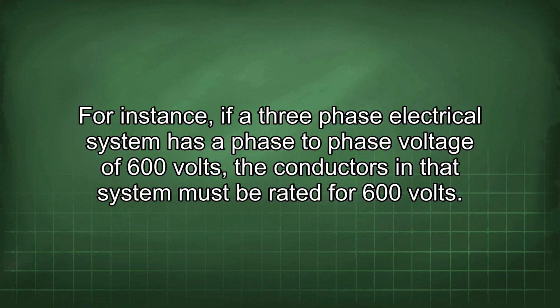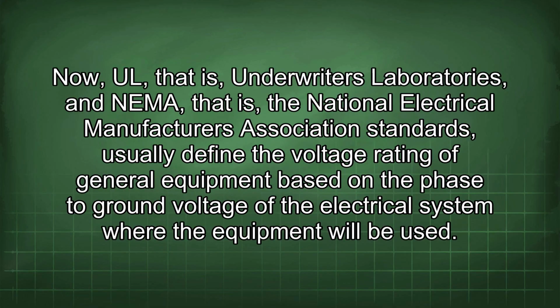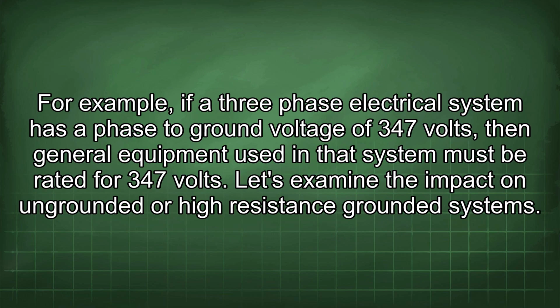For instance, if a three-phase electrical system has a phase-to-phase voltage of 600 volts, the conductors in that system must be rated for 600 volts. Now UL, that is, Underwriters Laboratories, and NEMA, that is, the National Electrical Manufacturers Association standards, usually define the voltage rating of general equipment based on the phase-to-ground voltage of the electrical system where the equipment will be used. For example, if a three-phase electrical system has a phase-to-ground voltage of 347 volts, then general equipment used in the system must be rated for 347 volts.